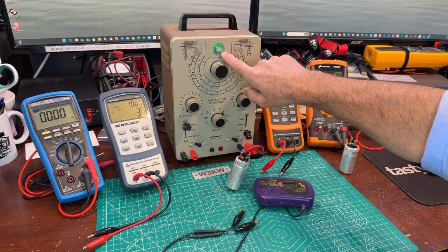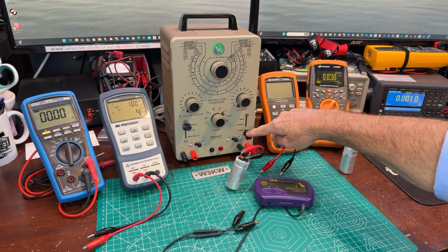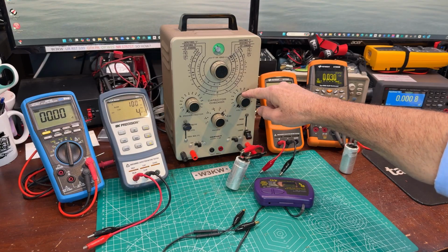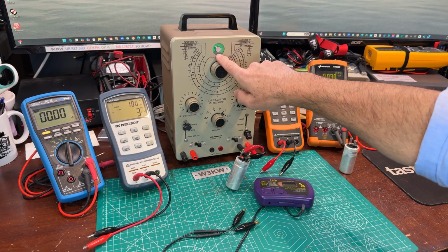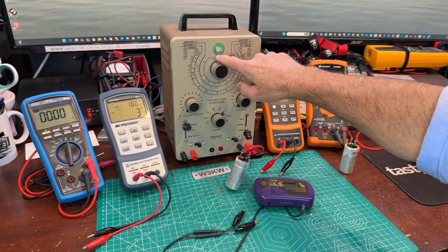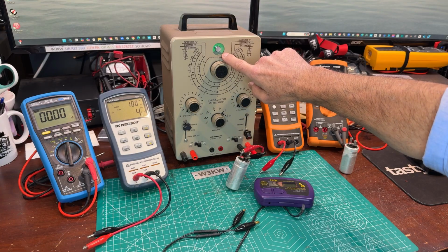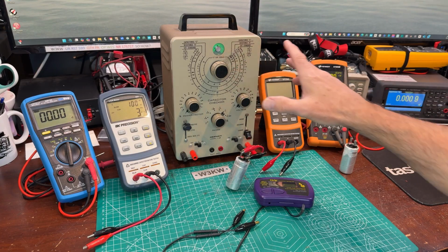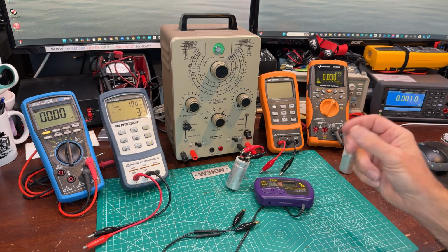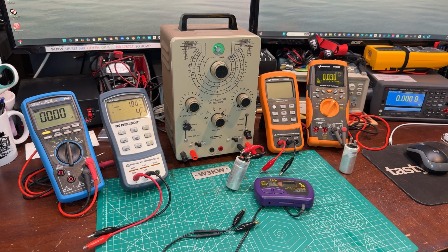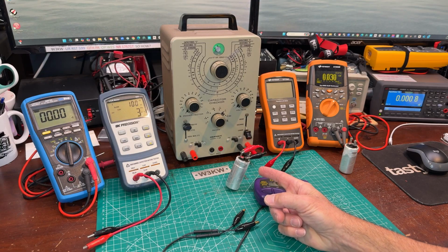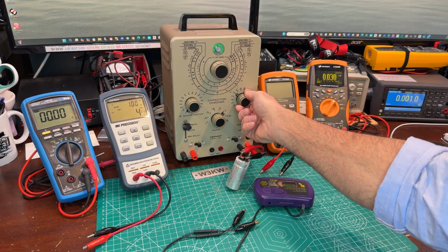If you look at the window here, as I'm on leakage and I add voltage to the capacitor, the window will start closing at some point in the voltage range. If it opens, it means the capacitor is good. If it stays closed, it means DC current is passing through the capacitor. So I'll start bringing this up.